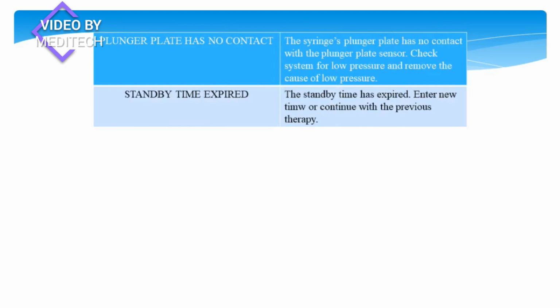Plunger plate has no contact. That means the syringe plunger plate has no contact with the plunger plate sensor. Check system for low pressure and remove the cause of low pressure. Standby time expired. The standby time has expired; enter a new time or continue with the previous therapy.